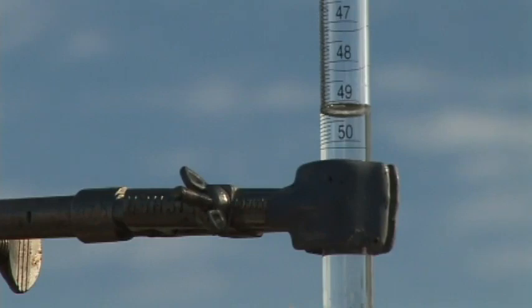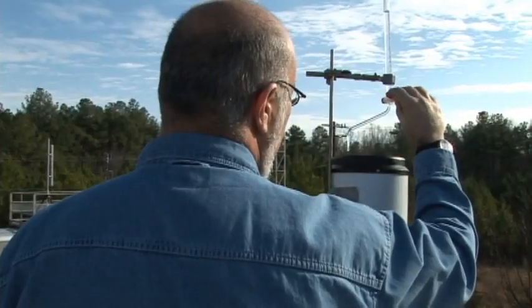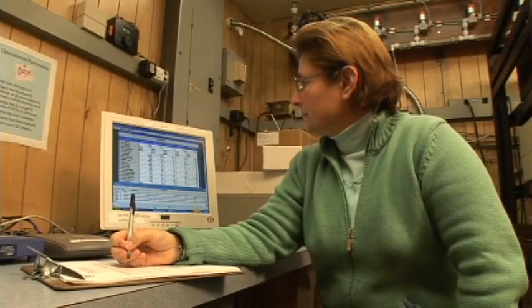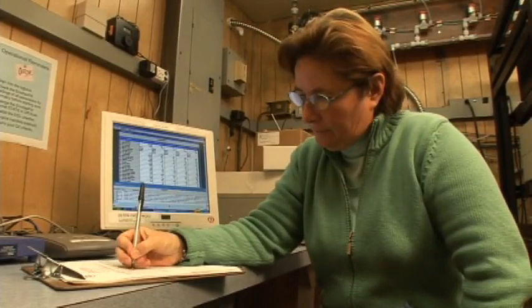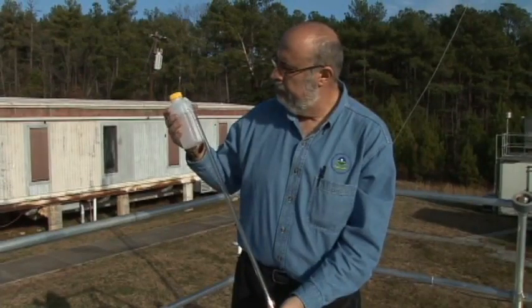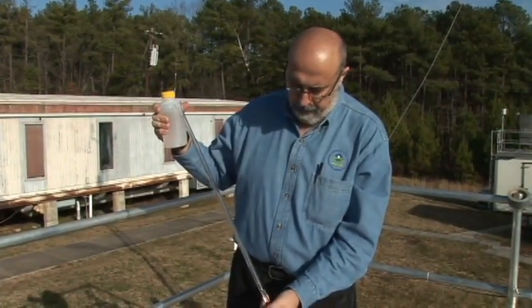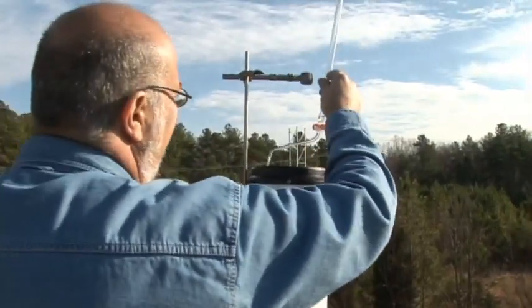Allow 20 milliliters of water to drip into the funnel of the gauge. This should constitute a number of tips by the gauge. Once 20 milliliters have been dripped into the funnel, close the stopcock and have the inside technician record the total rainfall amount. Check the manufacturer's manual for the table that relates the number of tips to the rainfall amount. Repeat this procedure 2 more times. However, change the volume of water that is introduced into the funnel on the second and third tests.